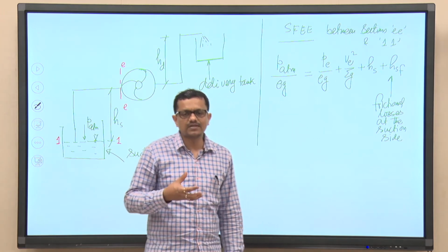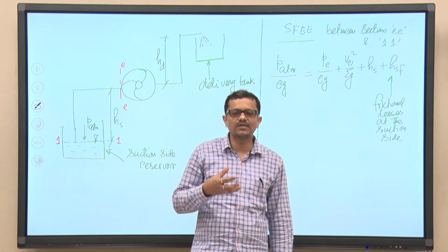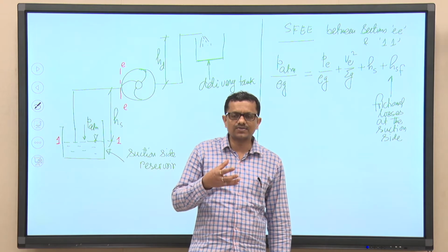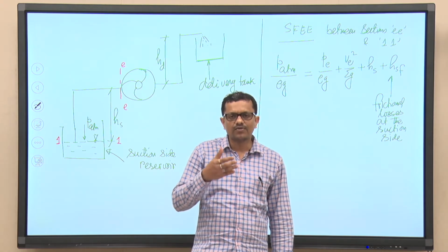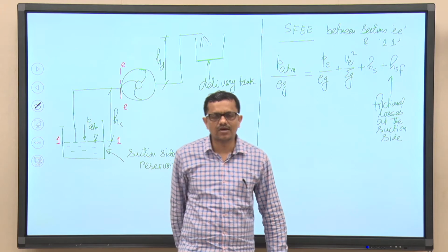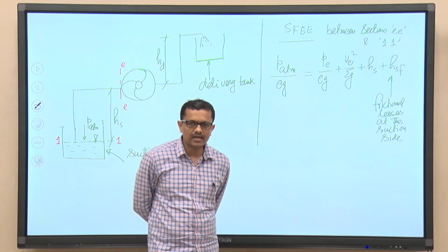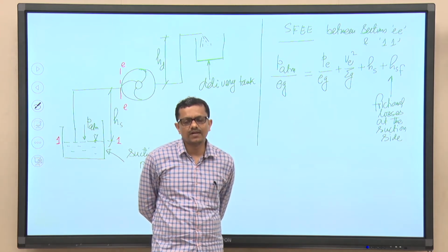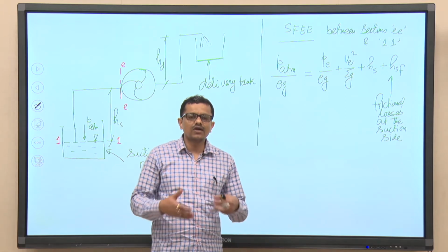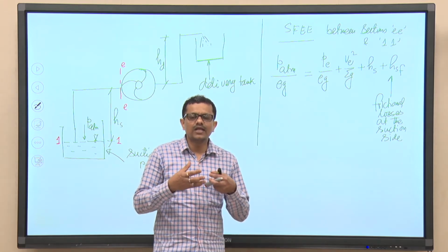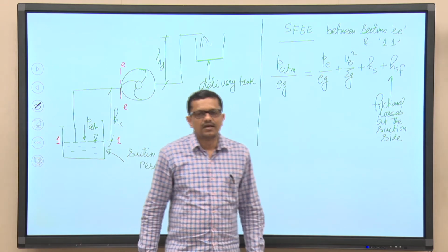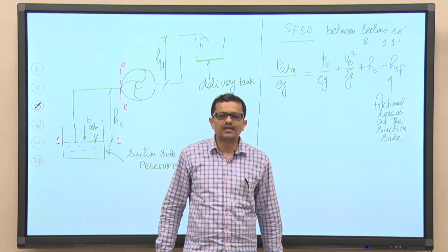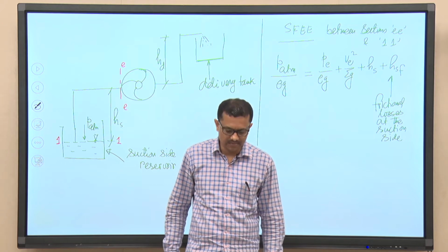Because of this change of thermodynamic state, vapor bubbles will form and be carried by the flowing liquid to another place where the pressure is relatively higher. Experiencing that relatively high pressure, the bubble will collapse, and this leads to an undesirable effect in pump operation, which is known as cavitation.